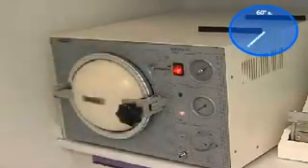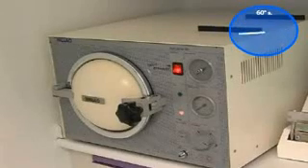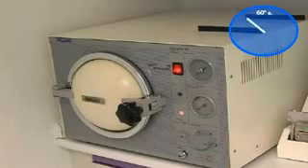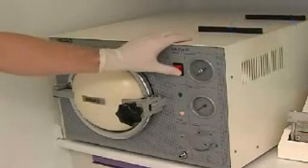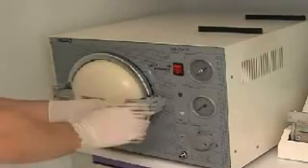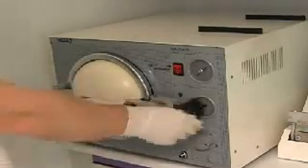For prion destruction, the materials that are being sterilized should be heated to 134 degrees Celsius for 18 minutes at 3 bars of pressure. The air in the autoclave interior should be completely replaced with saturated water vapor. These sterility conditions are only guaranteed with Category B sterilizers.